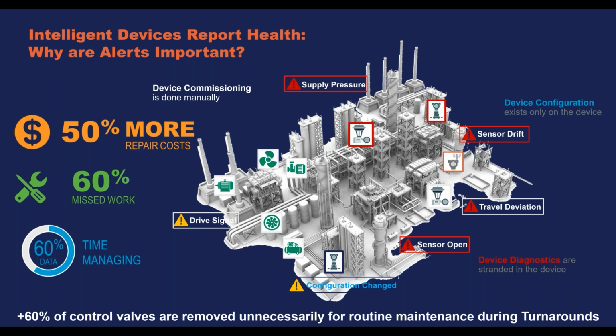Again, why should we change the status quo? Because it costs about 50% more to repair a failed asset than to address the issue beforehand. And it's also expensive to do maintenance for no reason. There's a lot of time where we just take a maintenance action because that's how it's scheduled in our maintenance procedure. I have a lot of examples of people taking control valves out of the process just because that's what the maintenance procedure says, and about 60% of the time, those valves are fine.